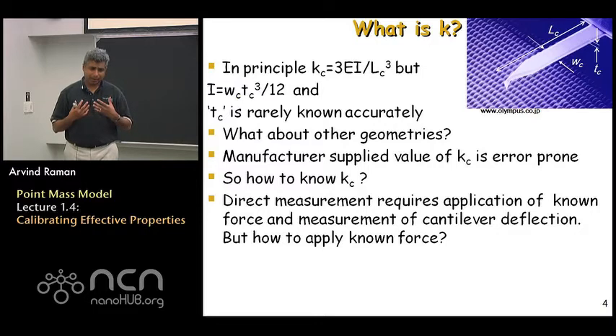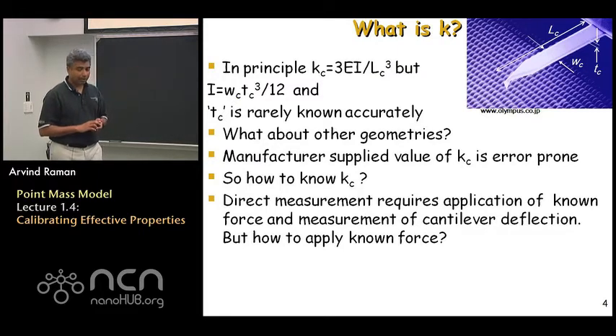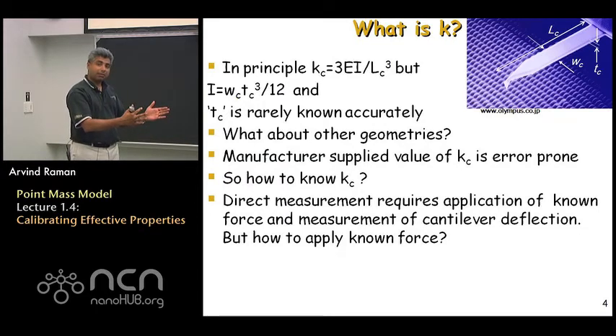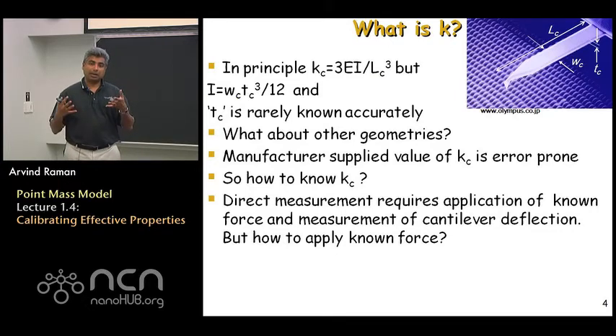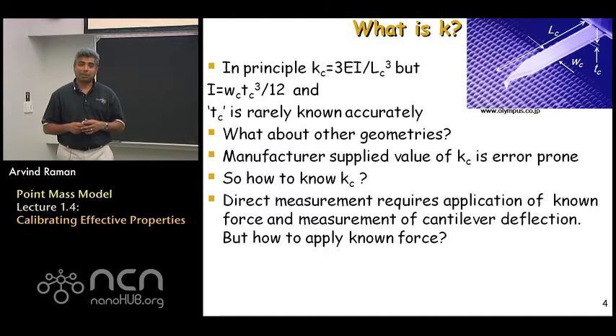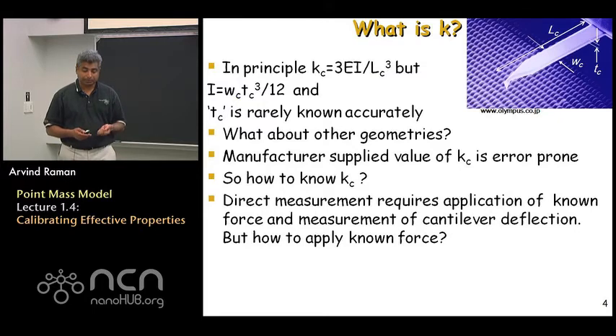The problem is the thickness of the cantilever is not very well known in most situations because of the fabrication process used to produce these cantilevers. Additionally, this formula is really valid just for nice rectangular cantilevers. If you look at the cantilever shown on the top right, you see one that for about two-thirds of the way is pretty rectangular but the last one-third becomes like a picket, and in that case these formulas become error prone. So it is important to measure k_c or k in an accurate, self-consistent manner through experiments. The simplest experiment would be to apply a known force and measure the deflection, but at the nanoscale there are very few standards by which one can apply, for example, one nanonewton force — it's very hard to do.